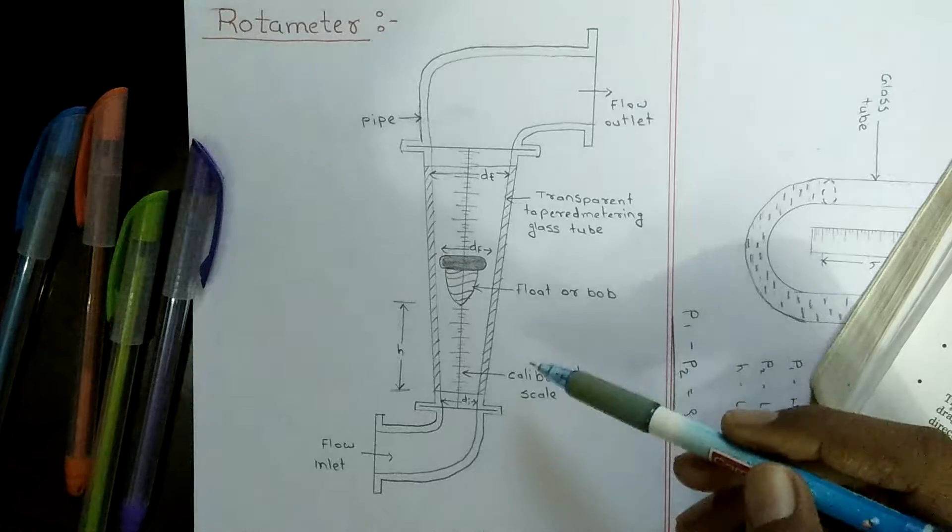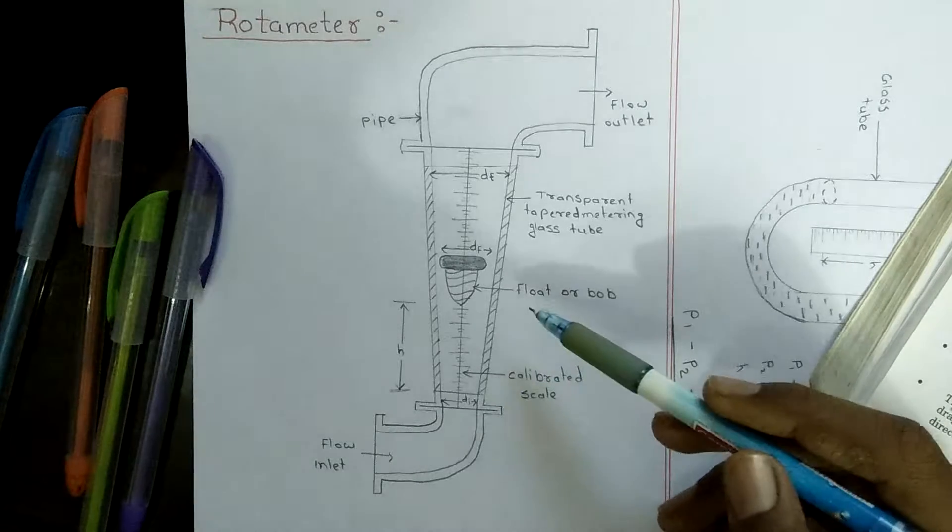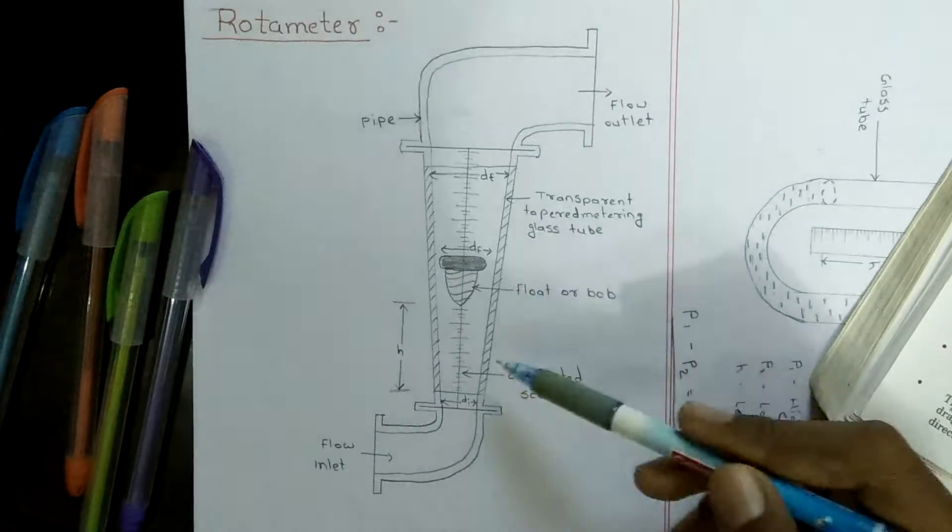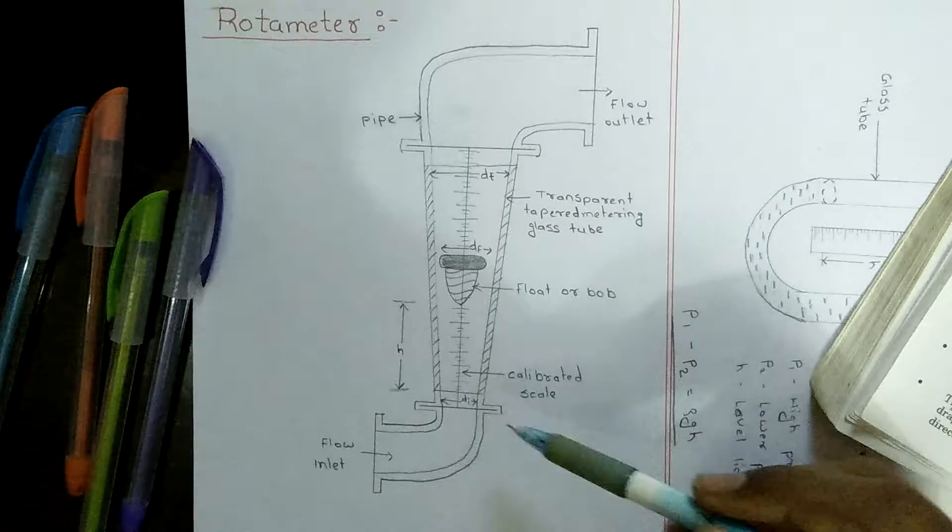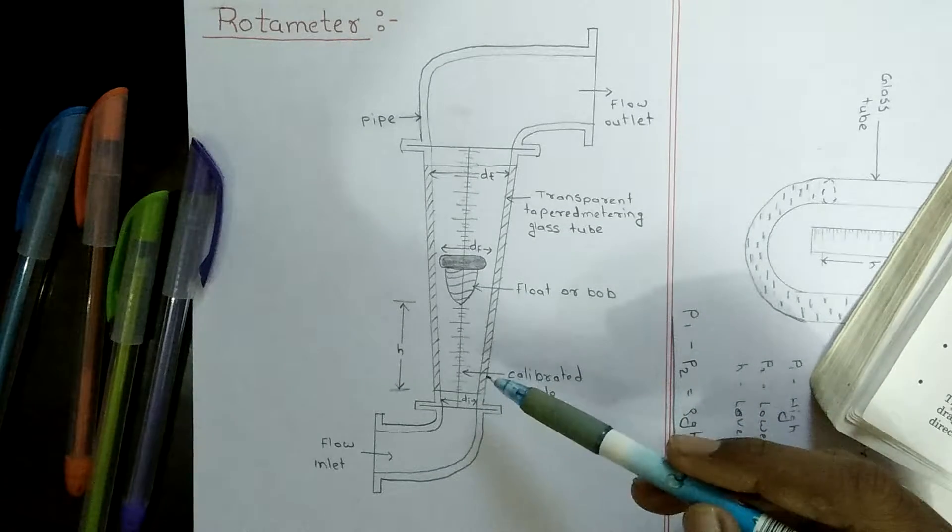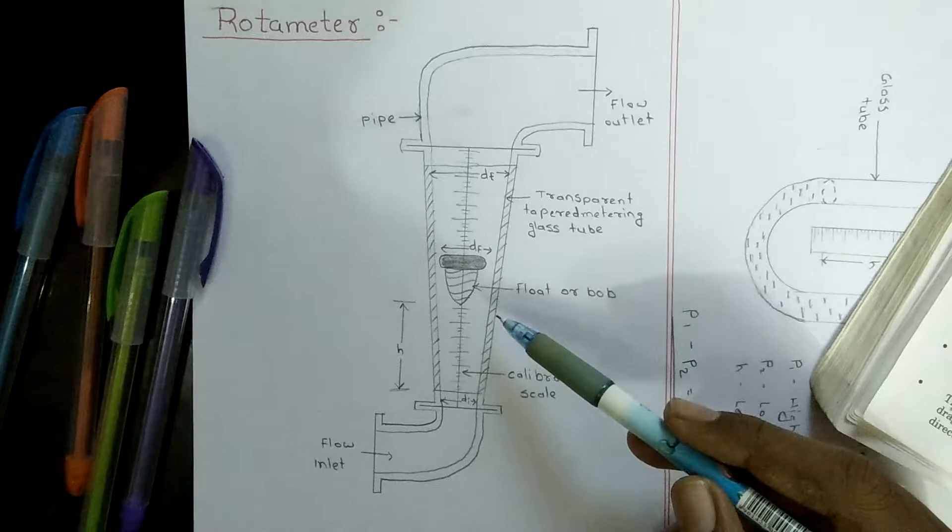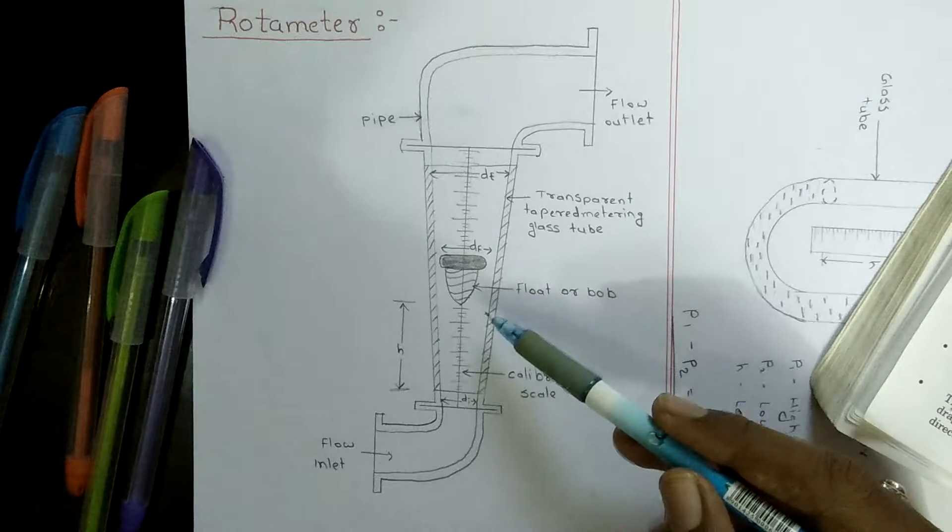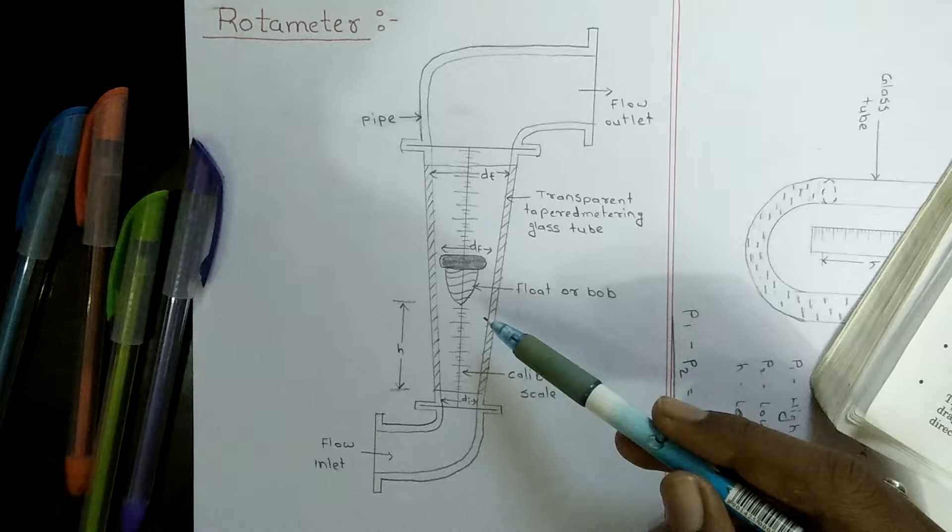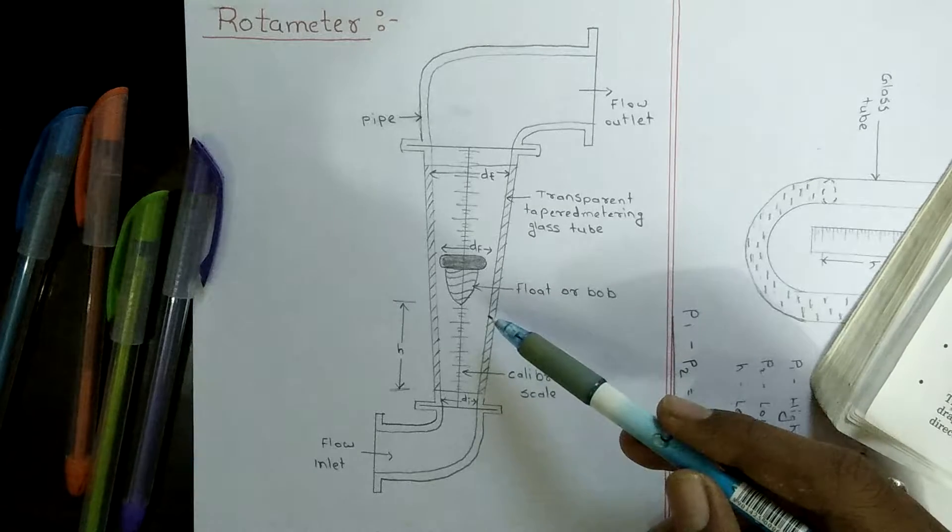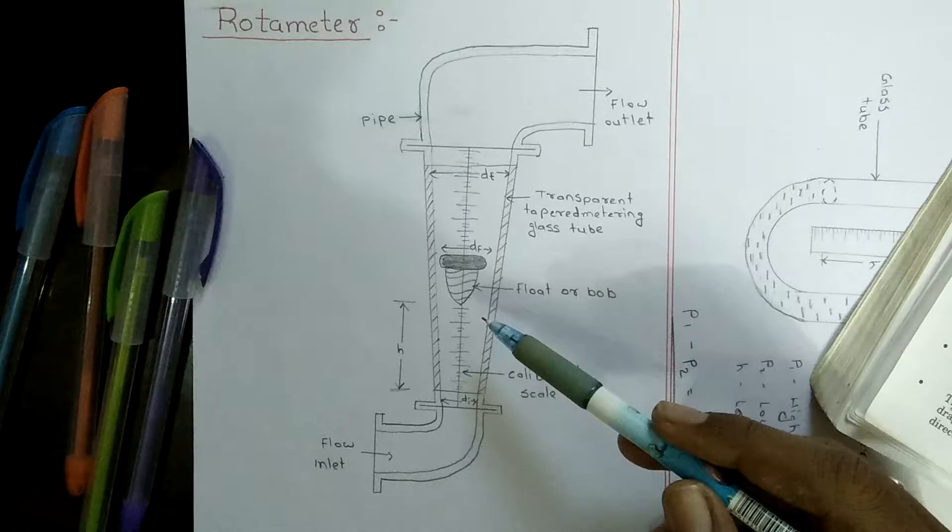The fluid moves the float upwards and downwards. The float will rise to a point in the tube where the upward drag force and buoyancy force is balanced by the downward directed weight of the float.